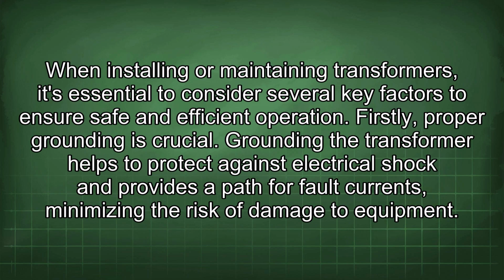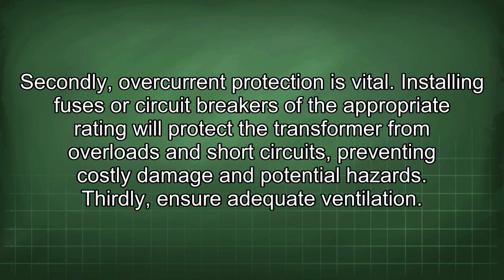When installing or maintaining transformers, it's essential to consider several key factors to ensure safe and efficient operation. Firstly, proper grounding is crucial. Grounding the transformer helps to protect against electrical shock and provides a path for fault currents, minimizing the risk of damage to equipment. Secondly, overcurrent protection is vital. Installing fuses or circuit breakers of the appropriate rating will protect the transformer from overloads and short circuits, preventing costly damage and potential hazards. Thirdly, ensure adequate ventilation.